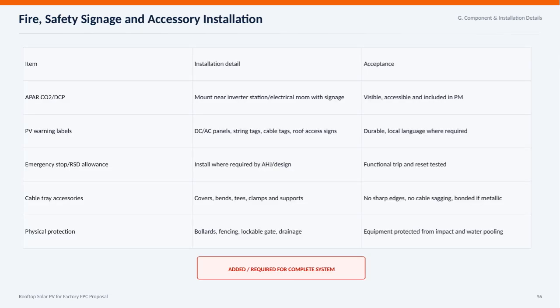Here we focus on the critical aspects of fire safety signage and accessory installation for the rooftop solar PV system. First, fire extinguishers like a CO2 or DCP must be mounted near the inverter station or electrical room with proper signage, ensuring they are visible, easily accessible, and included in preventive maintenance. Next, all PV warning labels should be placed on DC and AC panels, string tags, cable tags, and roof access points. These labels need to be durable and displayed in the local language where required to ensure clarity. Emergency stop buttons or rapid shutdown devices must be installed according to the authority having jurisdiction or design specs, and their trip and reset functions must be fully tested.